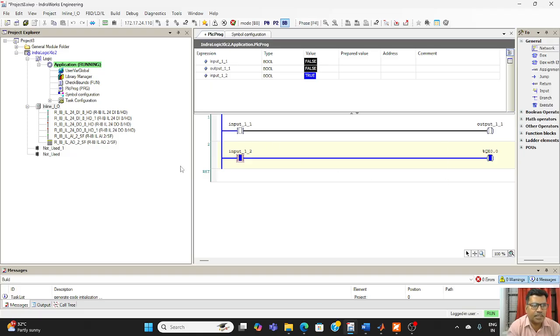This is an Indraworks PLC where I added all the input and output modules. Then in the program, I'll be giving some physical input here that will provide some virtual output. This output will be used to communicate using the OPC-UA program to MATLAB. Similarly, this input comes from the other PLC using the client, with MATLAB as a server, and from that server the output of the next PLC will be communicated and will come as an input here, so that some physical output will be switched on.